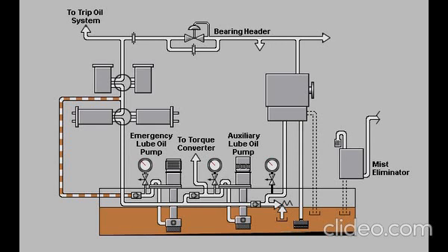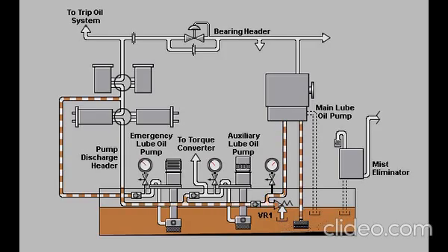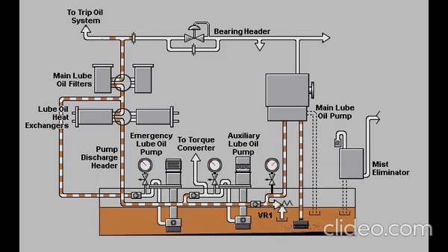When the gas turbine is operating at 100% speed, lubricating oil is pumped from the lube oil tank by the main lube oil pump and is delivered to the pump discharge header. VR1 limits the discharge pressure of the main lube oil pump to 101 PSI. Lube oil is cooled in the active heat exchanger, cleaned in the active oil filter, and passes through an orifice plate to the bearing header.